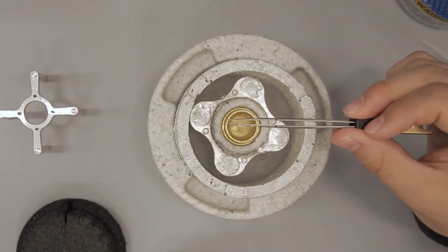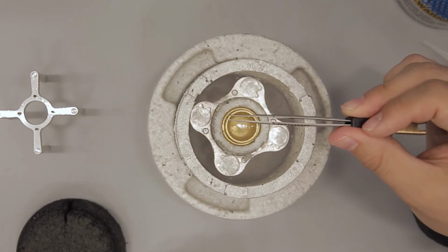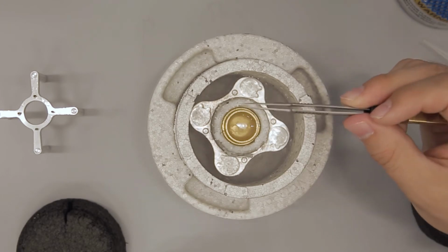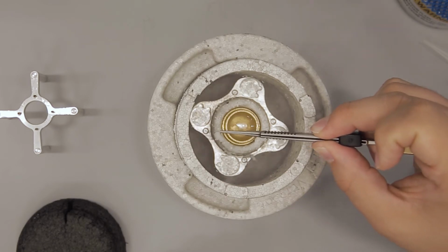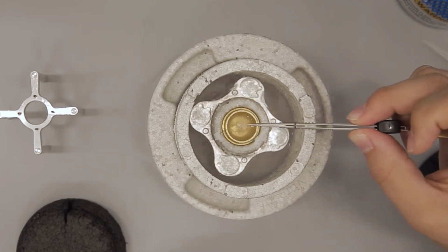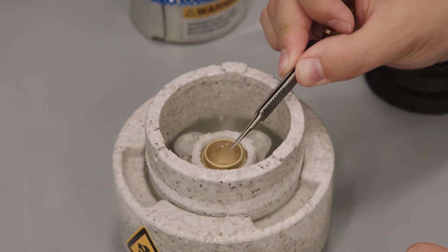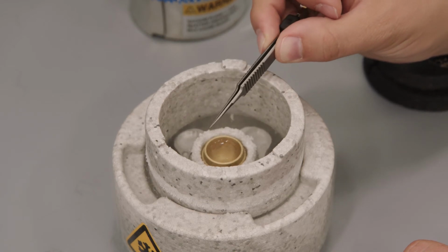Now, nitrogen vapor is cold, and there is no ice in nitrogen vapor. So nitrogen vapor is actually very, very clean. And the moment you go through that interface, that's where you will pick up small ice crystals, because this mist that you can see here are actually small ice crystals in the air that can contaminate your sample.